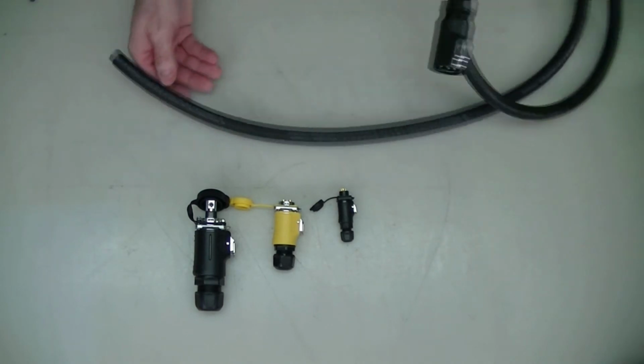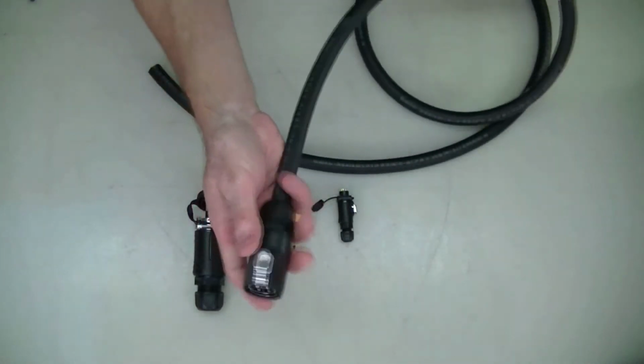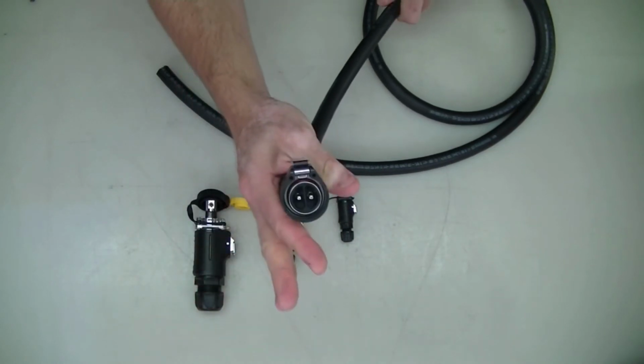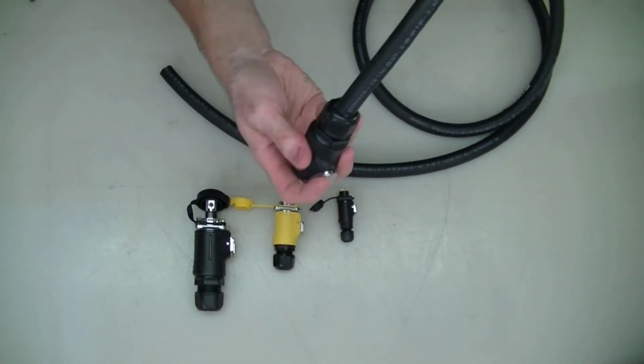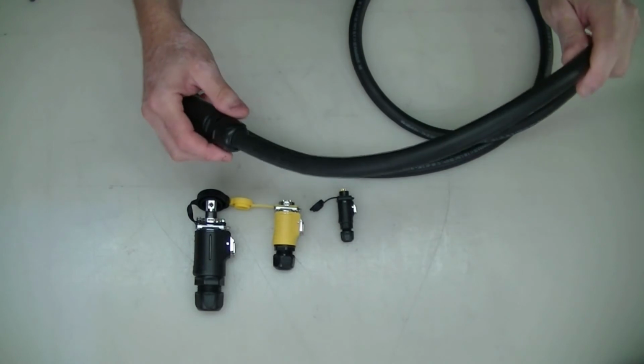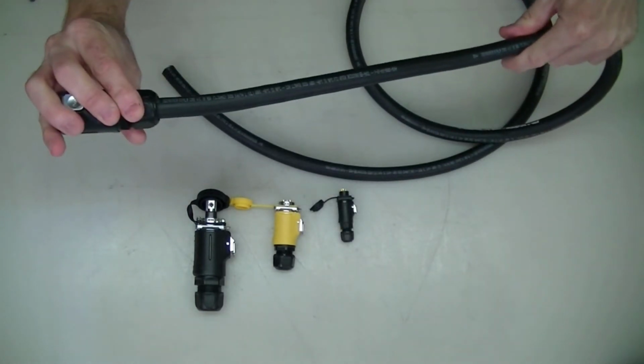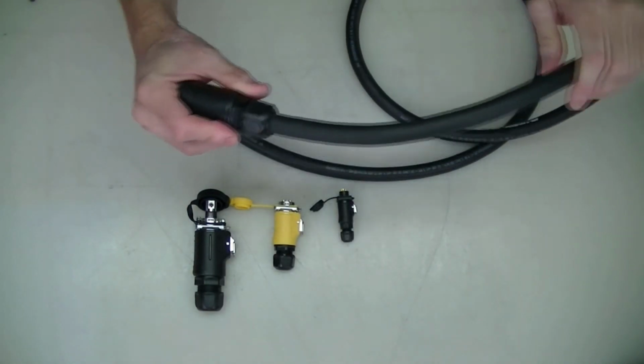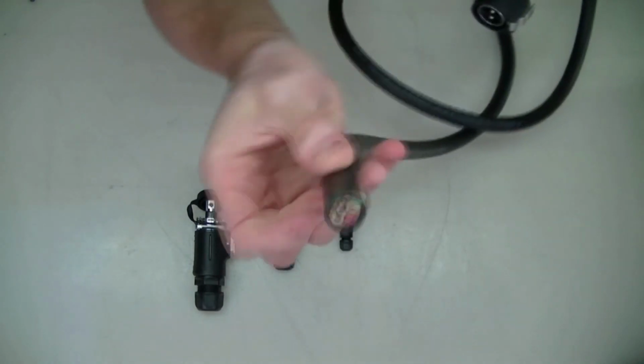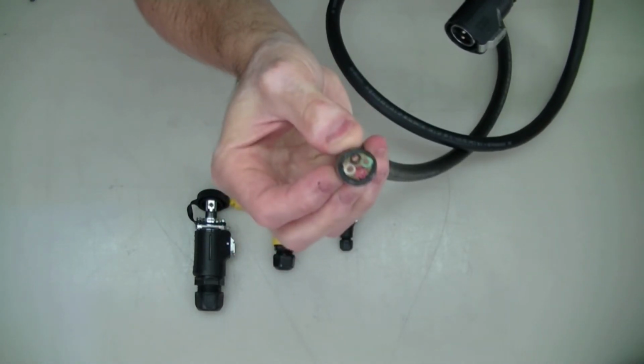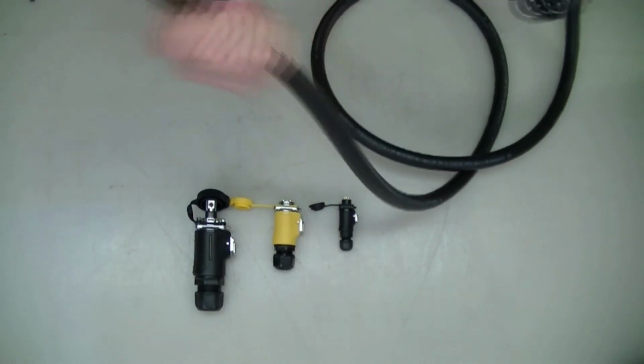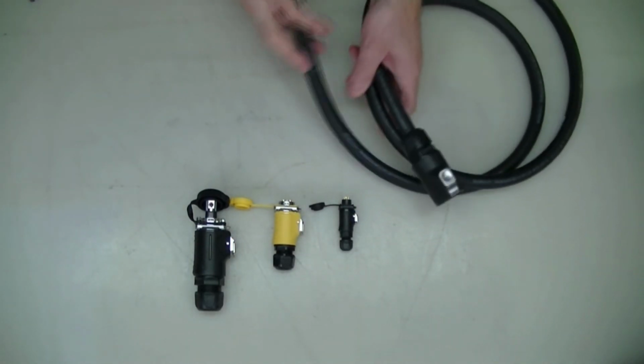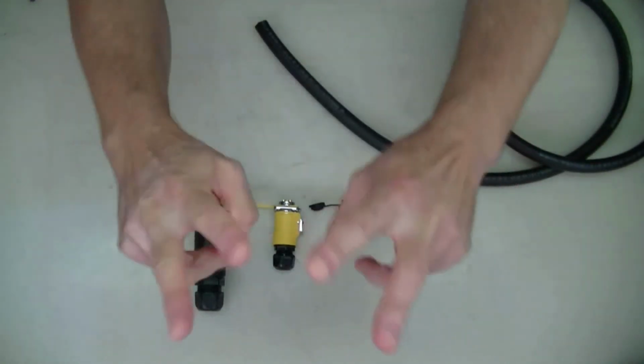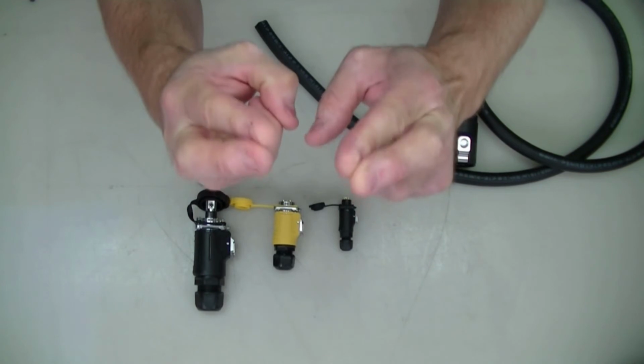One of those compromises: this high current cable to the motor, 2 conductors. I've spec'd a cable that's actually an outdoor rated extension cord cable, a 4 conductor 10 gauge cable with a round jacket. 10 gauge isn't enough to carry 50 amps, so I've paired up the conductors so I actually have 2 pairs of parallel conductors.